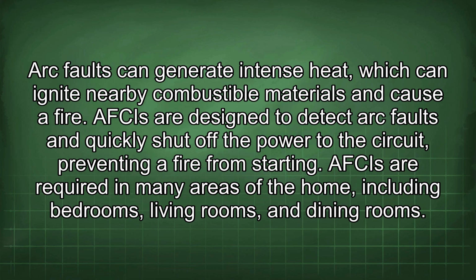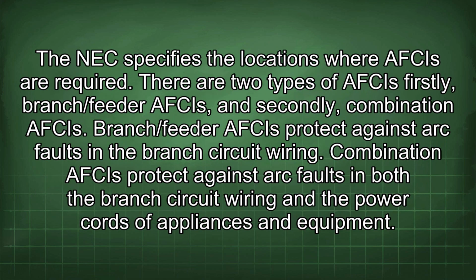AFCIs are required in many areas of the home, including bedrooms, living rooms, and dining rooms. The NEC specifies the locations where AFCIs are required. There are two types of AFCIs: firstly, branch/feeder AFCIs, and secondly, combination AFCIs. Branch/feeder AFCIs protect against arc faults in the branch circuit wiring. Combination AFCIs protect against arc faults in both the branch circuit wiring and the power cords of appliances and equipment.